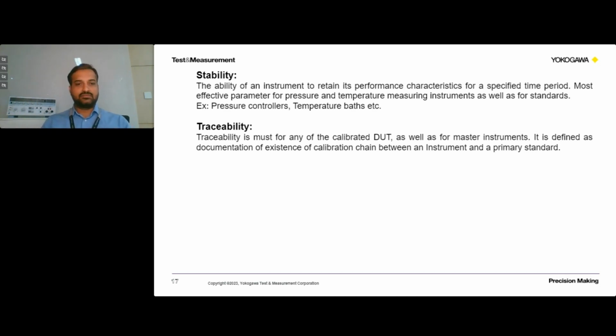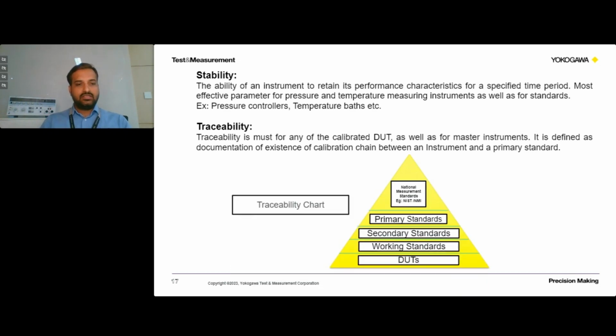Usually the traceability chart is indicated by a pyramid, where at the lower end we have DUTs, and we calibrate DUTs with the working standards. There will be a traceability certificate between these two, and further the working standards are calibrated with the master instruments in the secondary standards, which are further traced to the primary standards, and these primary standards have traceability to the National Metrology Institutes and NIST standard, those kind of institutes.